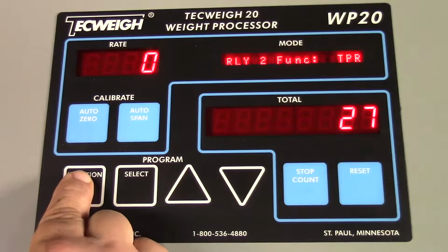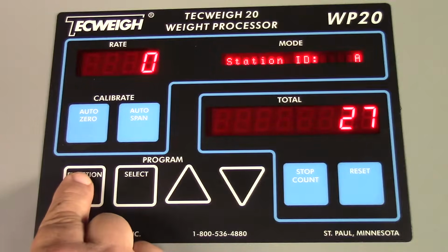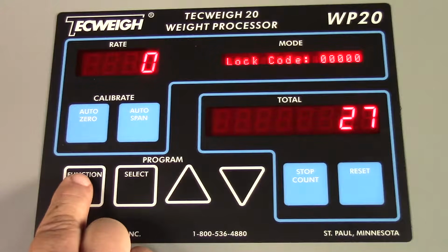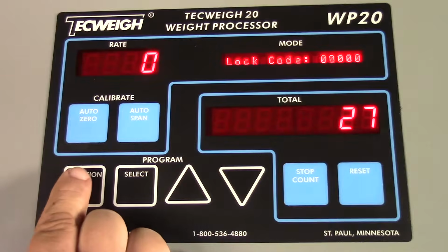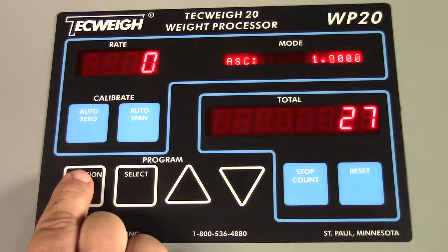There's also a second relay. We could adjust for another totalizer, or we could set it for a rate alarm, for example. There's a lot of different parameters we could program. There's also lock codes. We can lock out the use of it, lock out somebody spanning it and zeroing it, resetting the totalizer. Just make sure to write down the lock code.